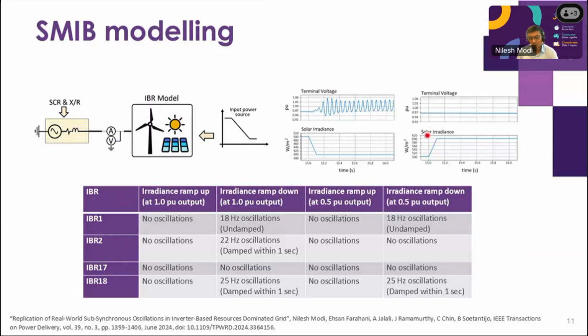So this is a setup of the SMIB analysis. We picked the 4 IBRs that we thought were most likely worth investigating. We looked at various operating points, although on the slides only 2 are mentioned: 1 per unit and half per unit. We slowly started reducing the irradiance at those IBRs, and we could see undamped oscillation in IBR number 1 at 1 per unit active power set point, and at the same time at half per unit active power set point.